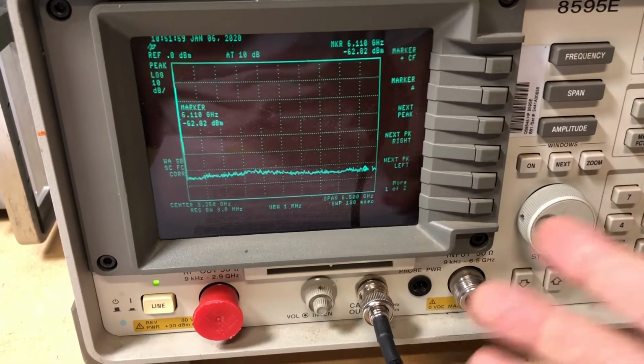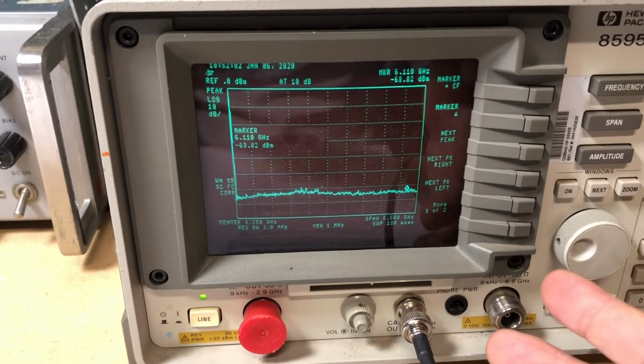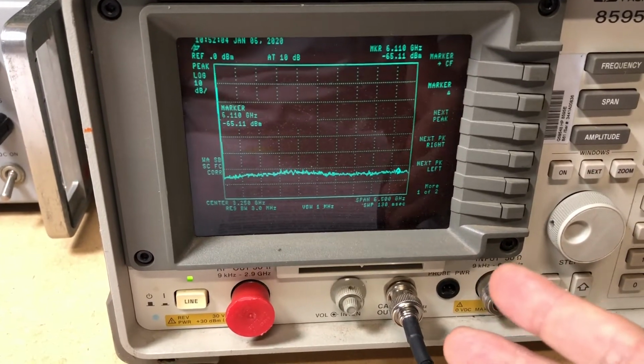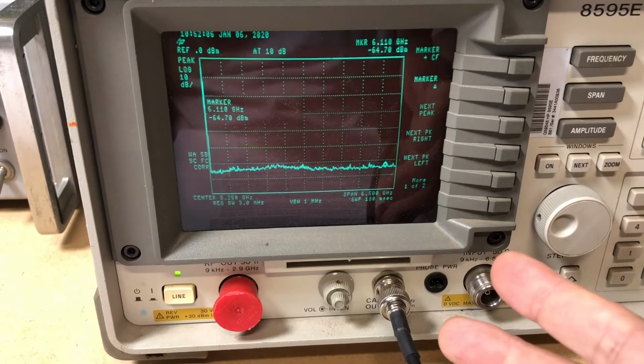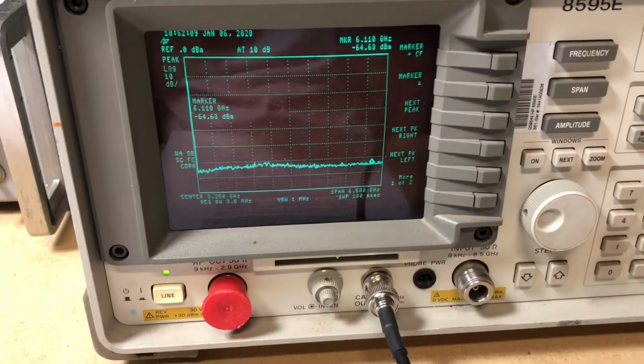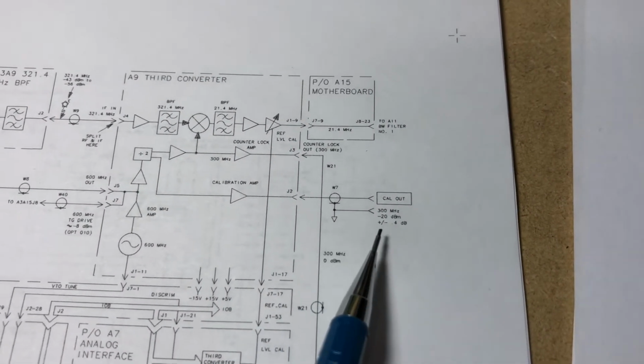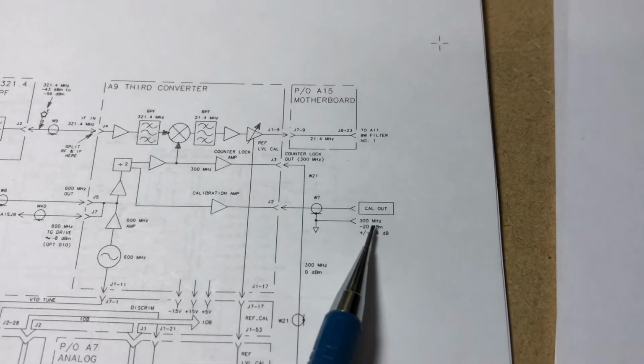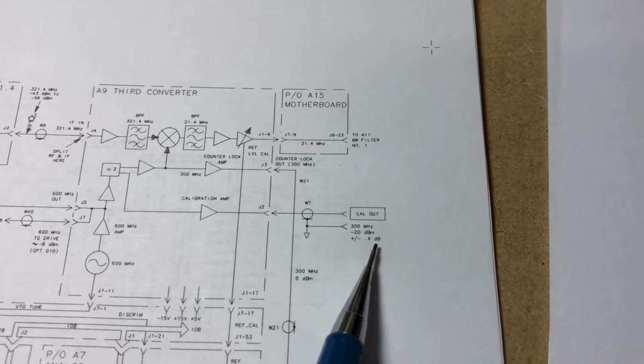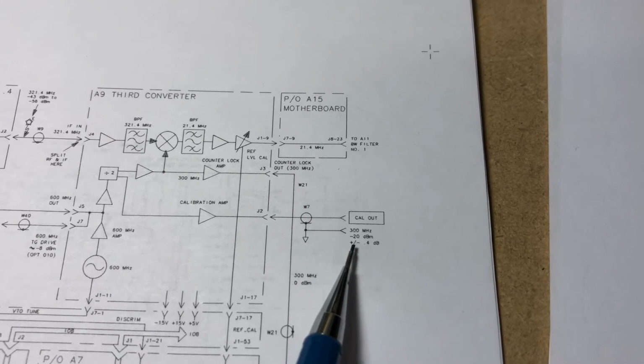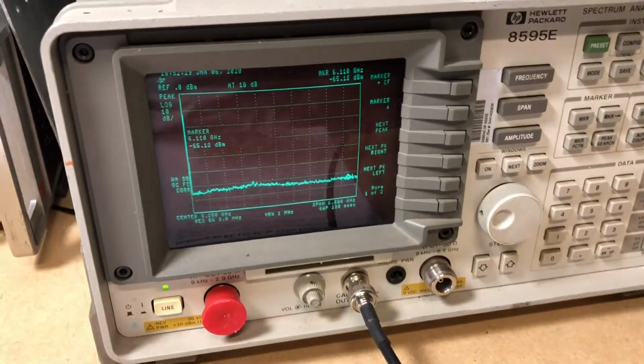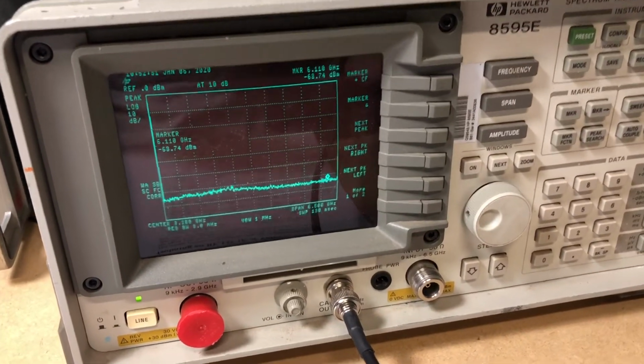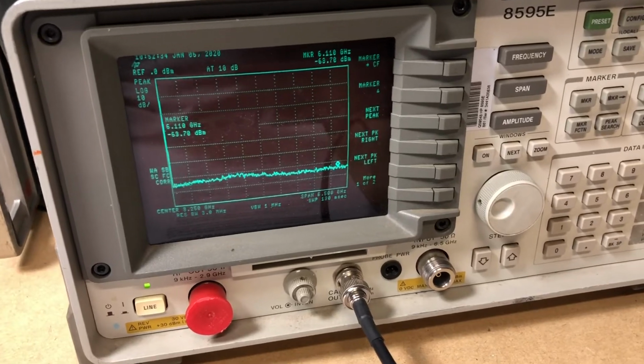I forgot about that, and I took a reading using the power sensor, and the power level was quite high. It was around minus 18.5 dB, where the schematic specifies for the cal out signal a power of minus 20 dB plus or minus 0.4 dB, so it has a fairly tight tolerance on the power level. So to avoid troubleshooting a problem that wasn't really there, luckily I remembered that you can't use a power sensor to take that reading, so I didn't.